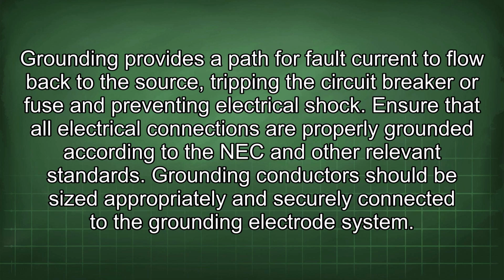Grounding provides a path for fault current to flow back to the source, tripping the circuit breaker or fuse and preventing electrical shock. Ensure that all electrical connections are properly grounded according to the NEC and other relevant standards. Grounding conductors should be sized appropriately and securely connected to the grounding electrode system.